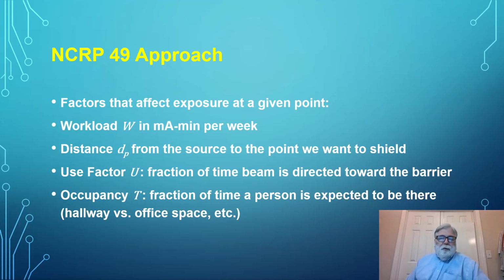The occupancy factor is 1. When the X-ray is working, you can assume that someone's in that room. If it's a reception, on the other hand, if it's a hallway, people just walk on by. If it's a restroom, people are only there for short periods of time throughout the whole year, not all 24 hours, 8 hours a day, 50 weeks a year.